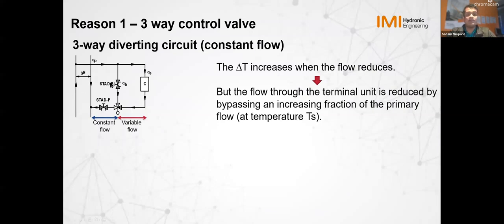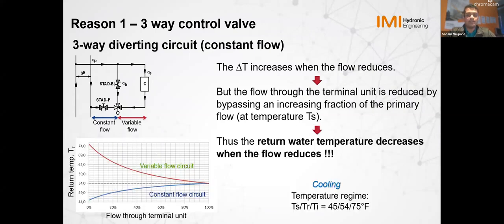And same thing, even if it didn't close completely and you had some water bypassing and some water going through the coil, you'd still have the same issue with a lower temperature water mixing with a higher temperature water. And that's going to affect your delta T. So we want to avoid that as much as possible, because the last thing we want is our chiller not performing as it's supposed to, and having to maybe add another chiller in the future, or just have a very non-energy efficient system.